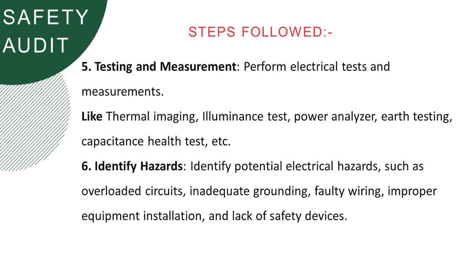After collecting walkthrough audit data and test results, we identify potential electrical hazards such as over-voltage, over-current, inadequate grounding, faulty wiring, and improper equipment installation — all checked for risk analysis. The collected documents, including electricity bills, are also analyzed for maximum demand, penalties, power factor, and energy usage by month and day.